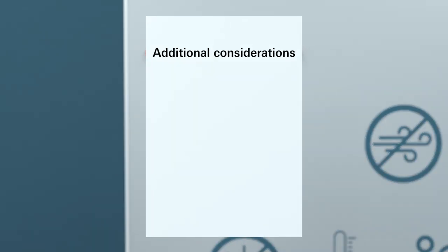Here are some additional things to consider with regard to the calibration process. In most cases, you will activate the calibration mode of the thermometer before doing the measurement. If this is not possible, you will need to convert the thermometer's reading by following the correction procedures specified by the manufacturer.